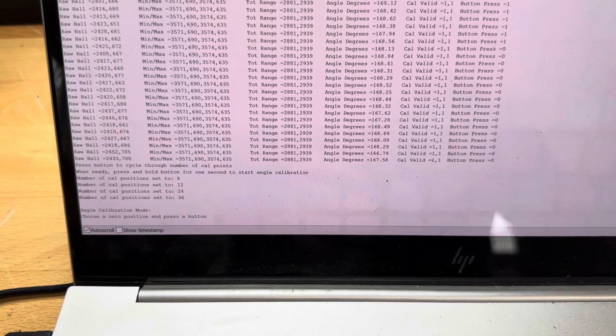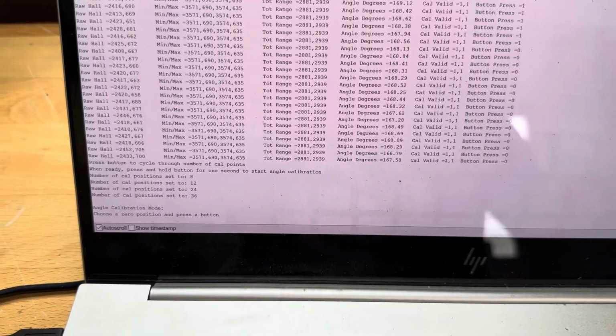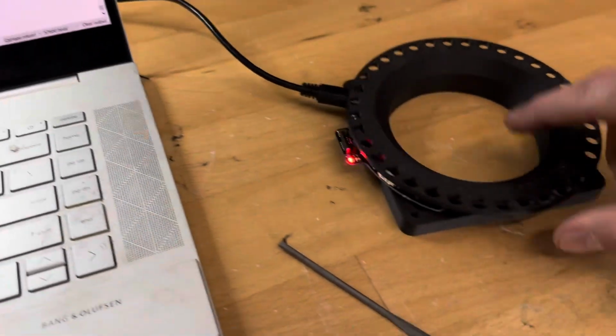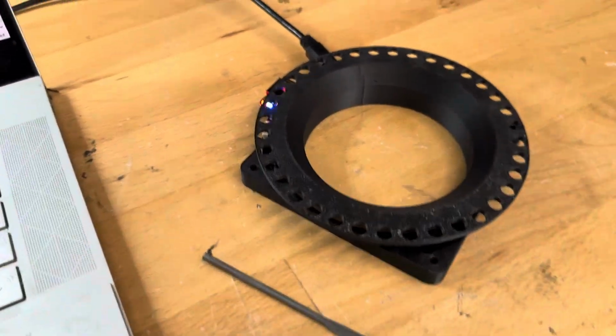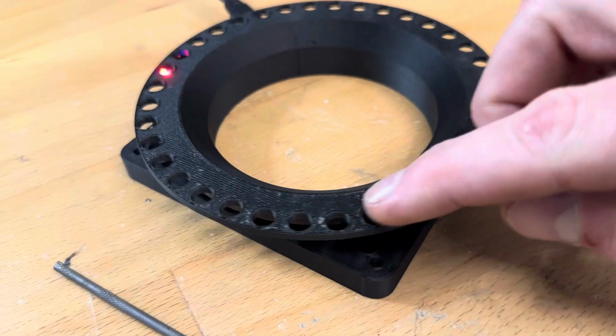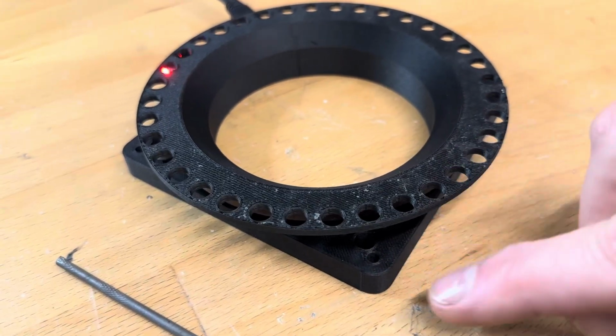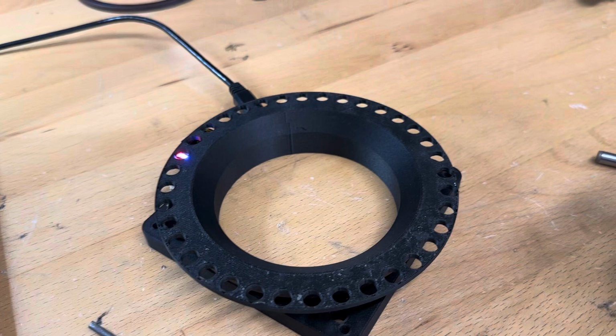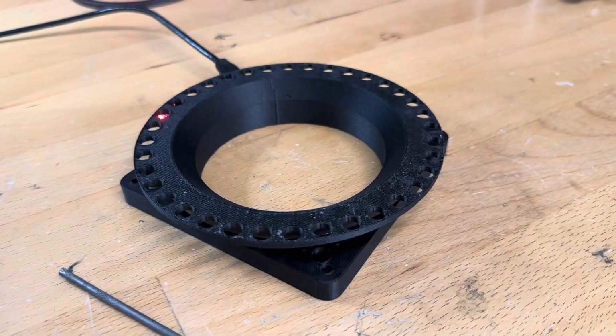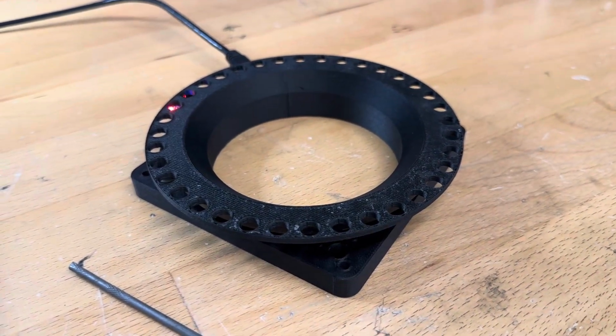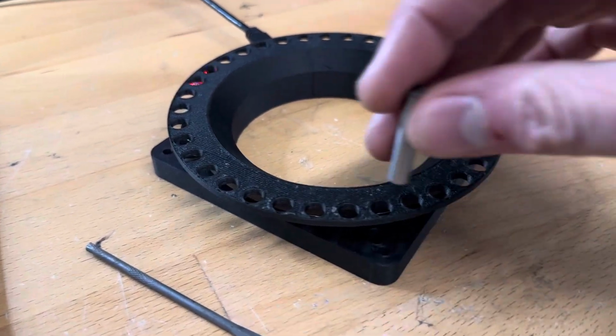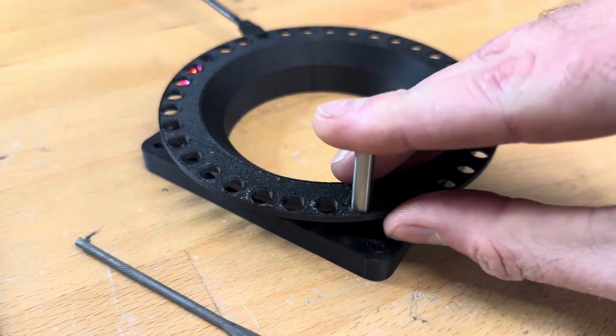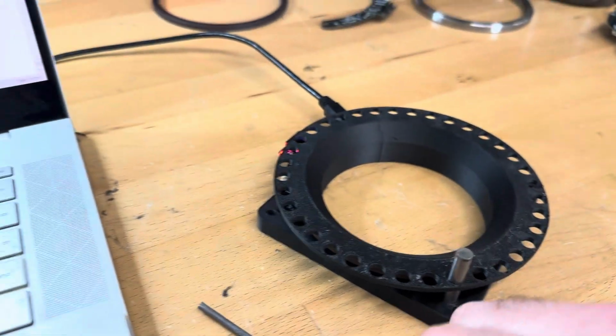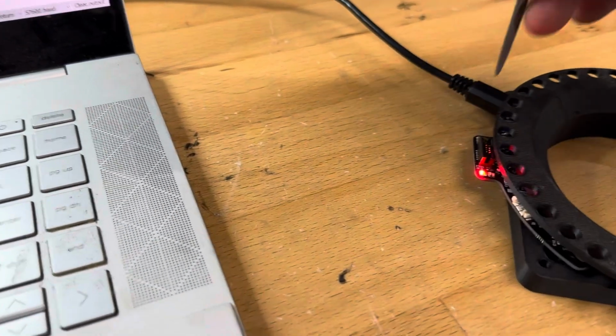And first thing it says is it wants you to pick a 0 position. Now remember, the 0 position can be arbitrarily changed at any point on the sensor itself. So for this, it's just a convenient starting spot for you to do your calibration routine. In this little rig, you can see I've set up a disc with 36 holes and a little spot to align it to. And this is just for our own internal testing, but you can imagine doing something similar on a swerve module, having holes or somewhere for a pin to line up if you needed to do it. And the way it works is, align your device however you're gonna do it, like I'm doing with the pin, then follow the prompts on the screen. So this says to press the button.